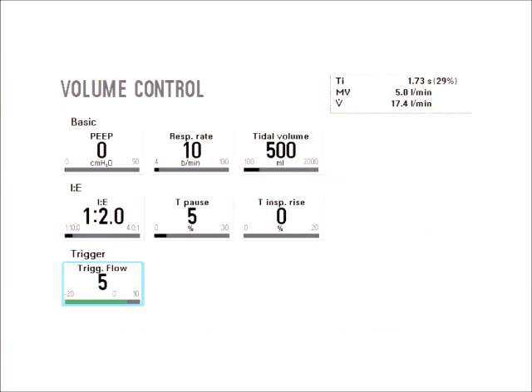Now, why is this important? I already kind of hinted on it. This is particular for volume control ventilation. You're only worried about compressive gas volume when you're using volume control modes, not volume targeted modes, but volume control modes specifically.